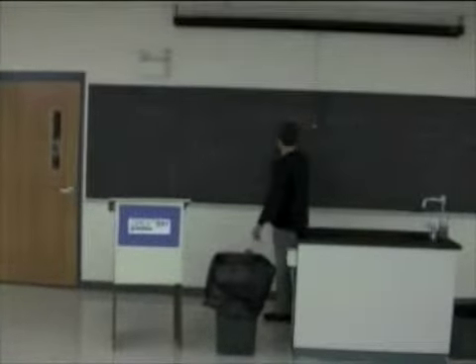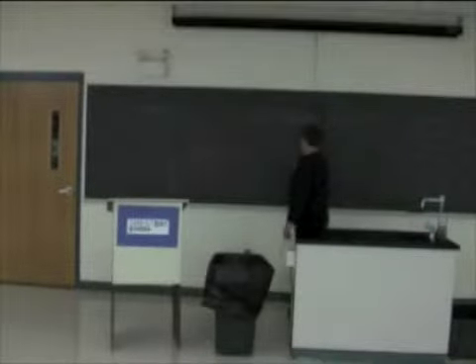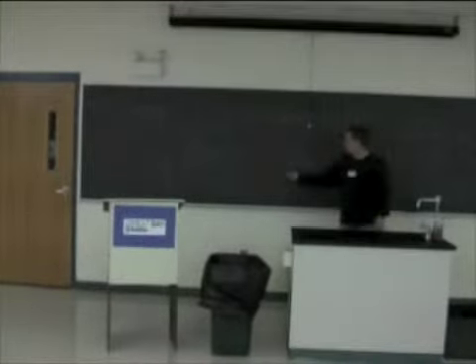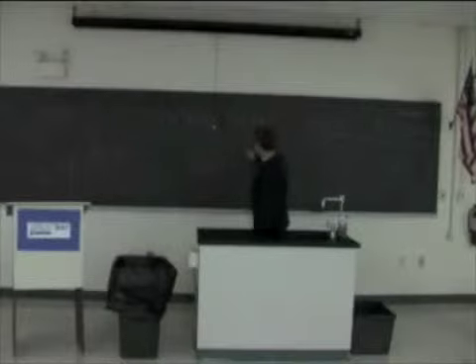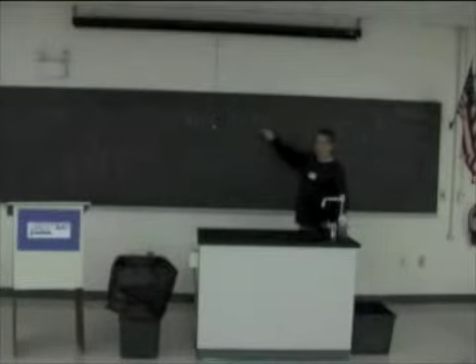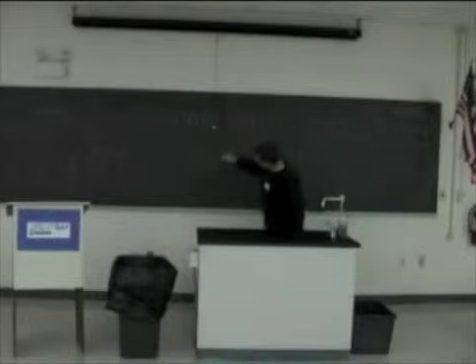We always think of energy costs being related to how much you use, and that's your generation. But you don't get this in houses, and so that's why you don't really see it too often. You get charged when you get an electric bill in a big building for what your demand is. Some of the engineering students and I saw the waveform for how a day or a week of electricity goes. The utility company takes your peak day, and they bill you based on that. So the higher that peak goes, the more you get billed, and it doesn't matter how much electricity you use overall, they bill you for the peak.